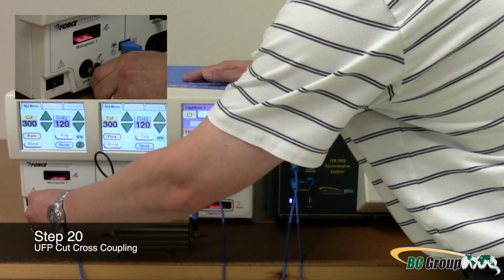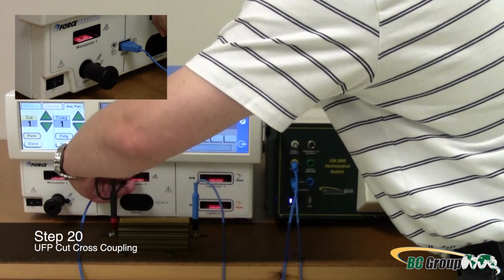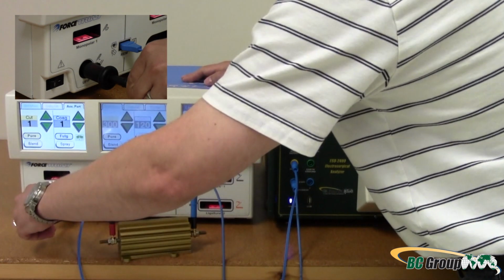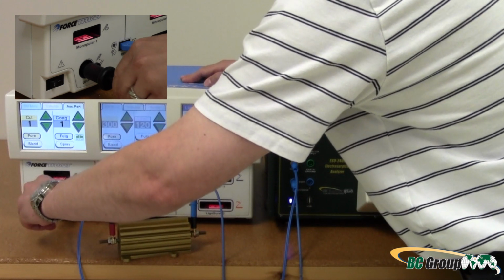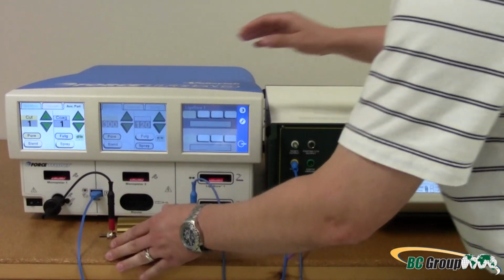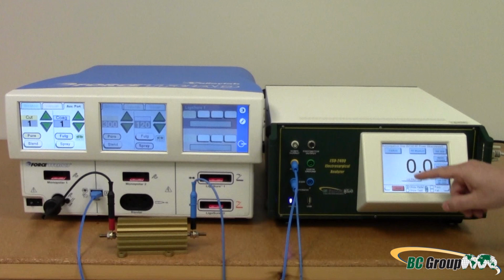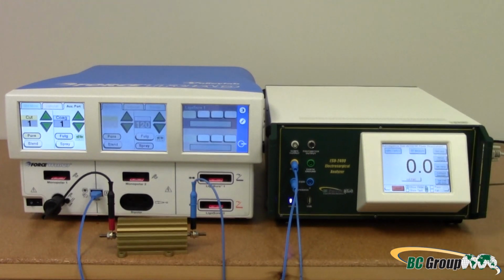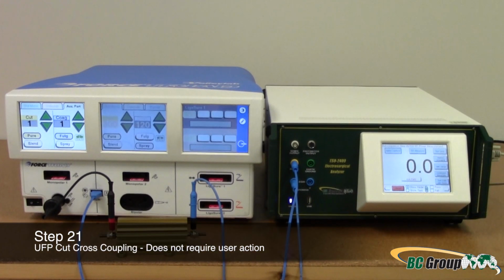Step 20. UFP cut, cross-coupling. Connect the UFP adapter to the UFP port. Move the jumper test lead from monopolar 2 to the UFP adapter. Select Show Meter and then press Capture. Step 21 does not require user action.